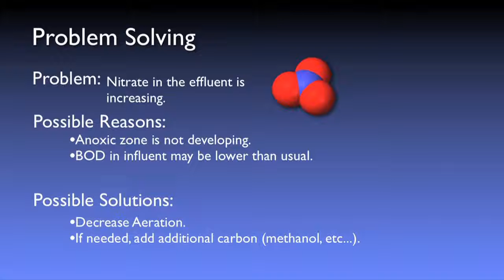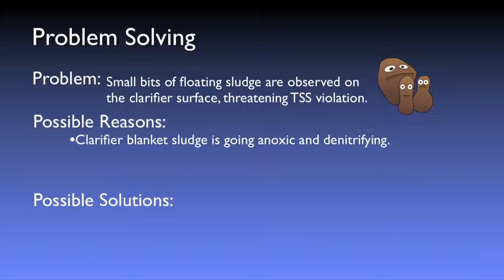Finally, during your afternoon stroll through the plant, you notice unsightly small bits of floating sludge accumulating on the surface of the clarifier. Upon this discovery, you immediately remember this helpful video discussing this exact scenario. It becomes obvious to you that your sludge blanket at the bottom of the clarifier is going anoxic and denitrifying, causing sludge to float due to the generation of nitrogen bubbles.